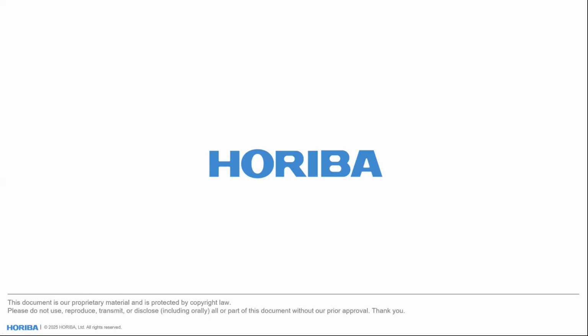Let's see here. Probably try to squeeze a couple more. What is the lifetime of an X-ray generator? The warranty is like 2,000 hours, but usually it stays much longer. Okay.